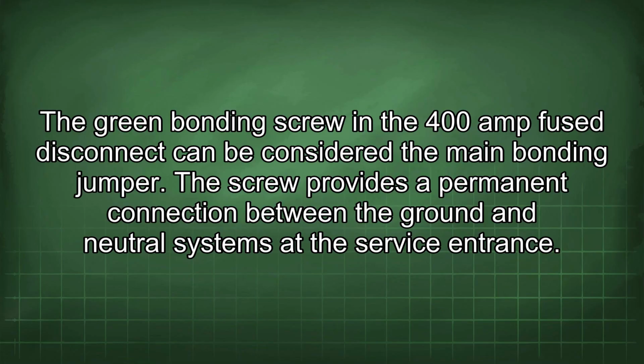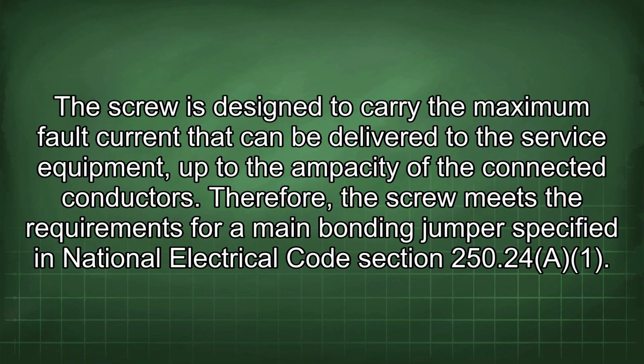The green bonding screw in the 400 amp fuse disconnect can be considered the main bonding jumper. The screw provides a permanent connection between the ground and neutral systems at the service entrance. The screw is designed to carry the maximum fault current that can be delivered to the service equipment, up to the ampacity of the connected conductors.